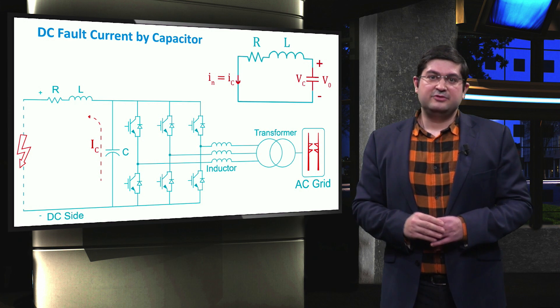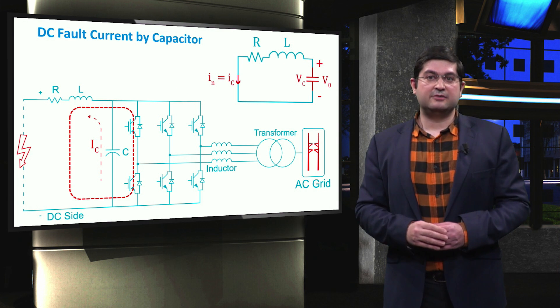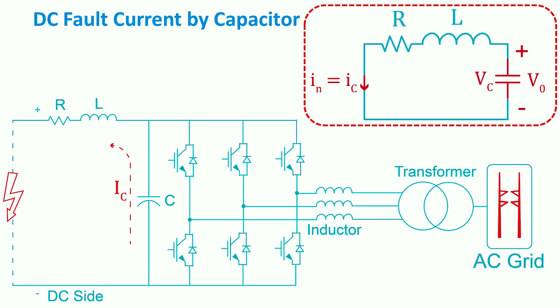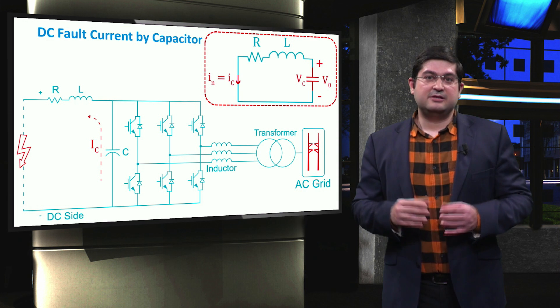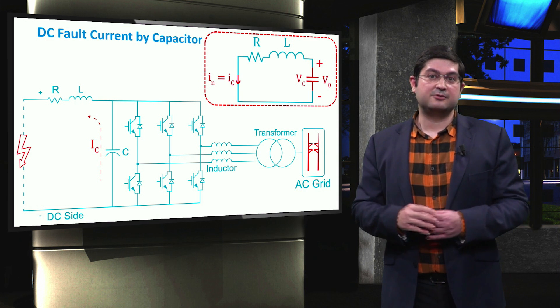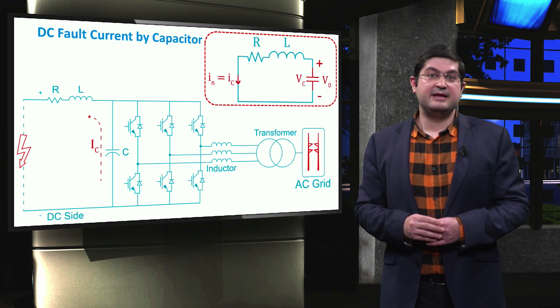The second electrical element which contributes to the fault current is the capacitor of the DC link. The equivalent circuit of the capacitor shows that during the fault, the energy stored in the capacitor is released, where the fault current is IC. Note that higher values of the capacitor will typically help increase the stability of the DC link — in other words, DC link voltage fluctuations can be mitigated by increasing the parallel capacitor. However, during a fault, this causes a very large fault current in DC microgrids, which we will discuss further later in this video.